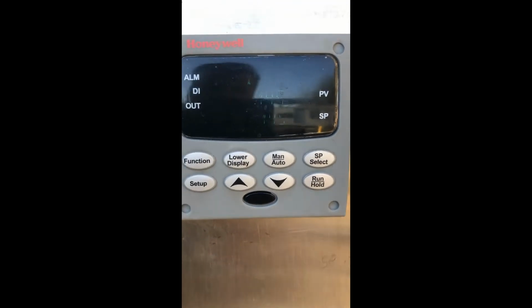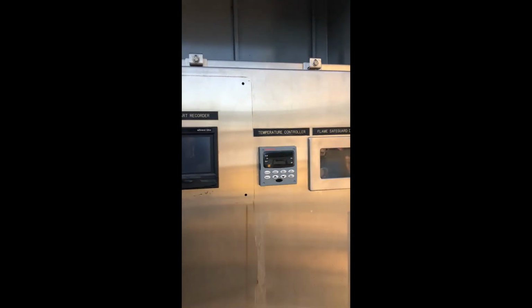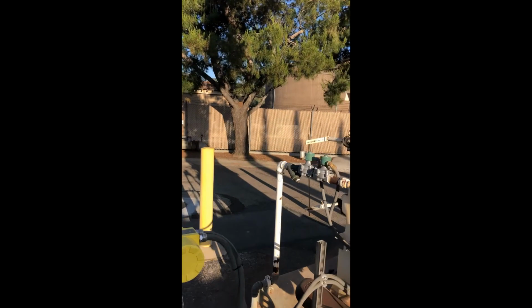The set point is right here, determined by the operator, who enters it at the top right, where it says set point select. He or she enters a set point right there. And then the control variable again is this actuator right here that's operating these louvers, and that's how we maintain 1450 degrees according to air quality. Here's the permit for it from South Coast Air Quality Management. So that's how we stay compliant.